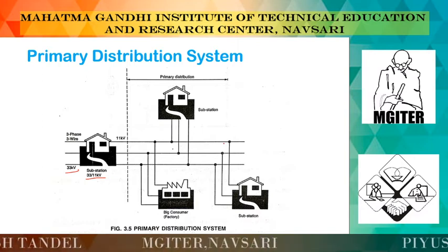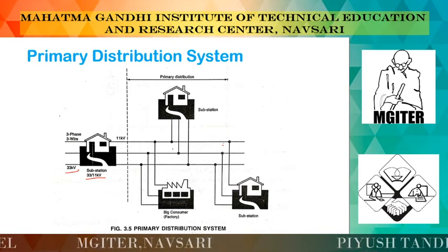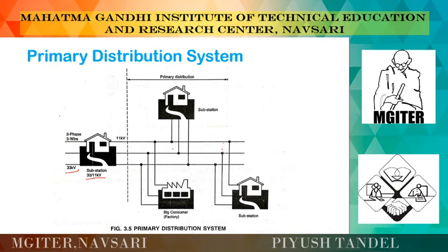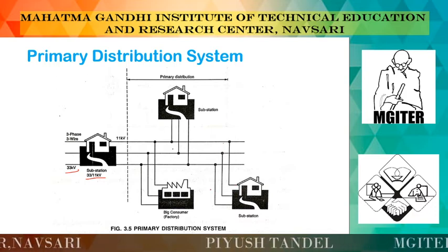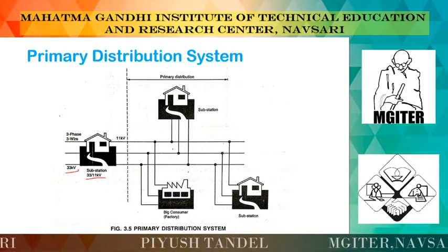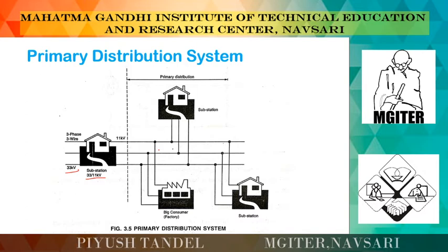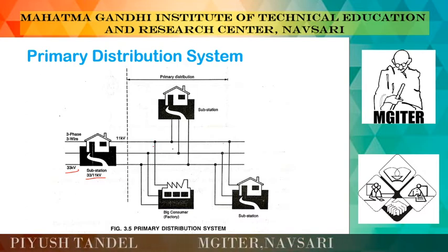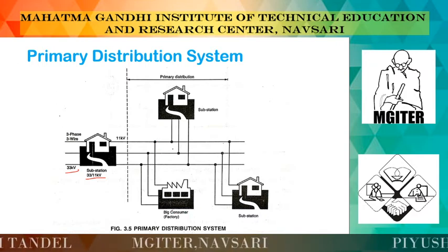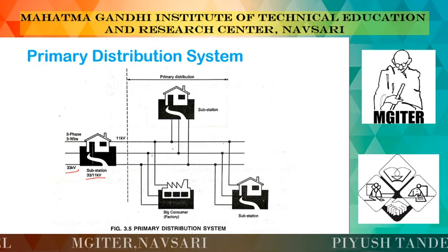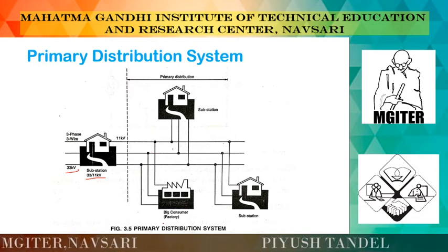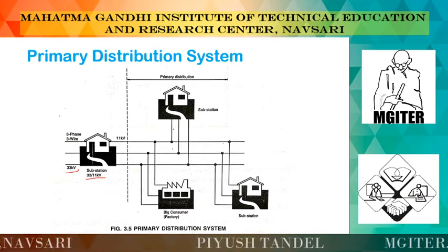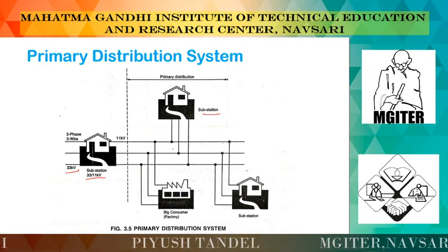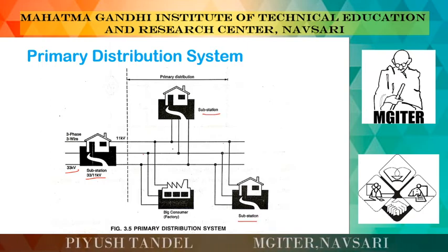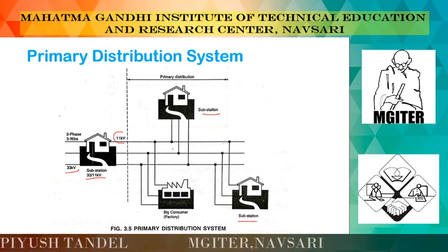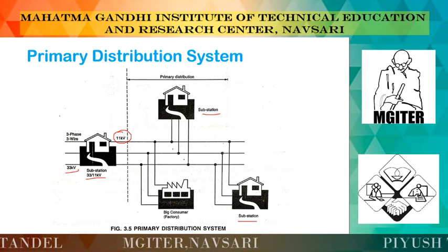The voltage used for the primary distribution system depends on the power to be conveyed and the distance of the substation to be fed. From the point of view of economy, primary distribution carries three phase wires only. We do not have four wires here, only three wires, that is a three phase three wire system. For big consumers like factories, we directly provide 11 kV, also a three phase three wire system, to factories or HT consumers. Then this three phase three wire supply also goes directly to different substations located at different sites. This is called the primary distribution system, where we feed 11 kV to big consumers and substations.